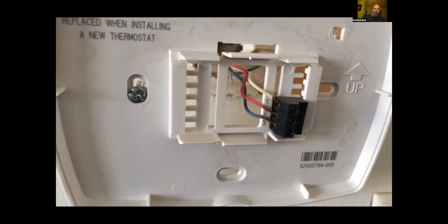From Glenn. Okay, so unfortunately, the answer to this one is going to be probably not. Three-wire systems are usually an indication of a probable proprietary system, meaning these are communication wires, and we don't know if this is going to be your RWG. We don't know that for sure. So this one will require further investigation, and we're not able to tell based on just the thermostat.